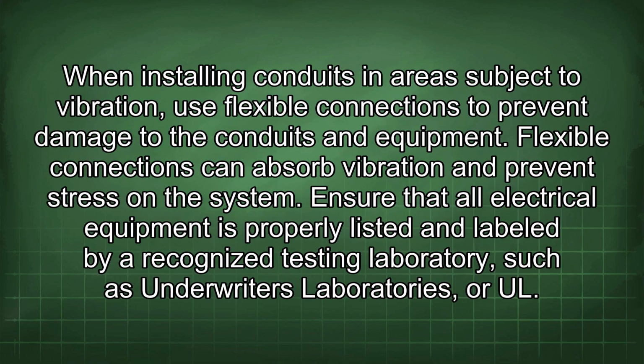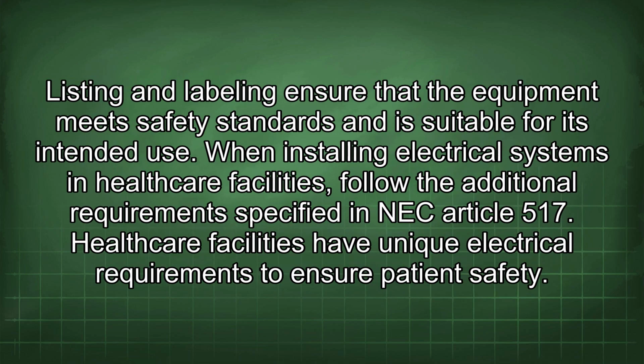When installing conduits in areas subject to vibration, use flexible connections to prevent damage to the conduits and equipment. Flexible connections can absorb vibration and prevent stress on the system. Ensure that all electrical equipment is properly listed and labeled by a recognized testing laboratory, such as Underwriters Laboratories or UL. Listing and labeling ensure that the equipment meets safety standards and is suitable for its intended use.